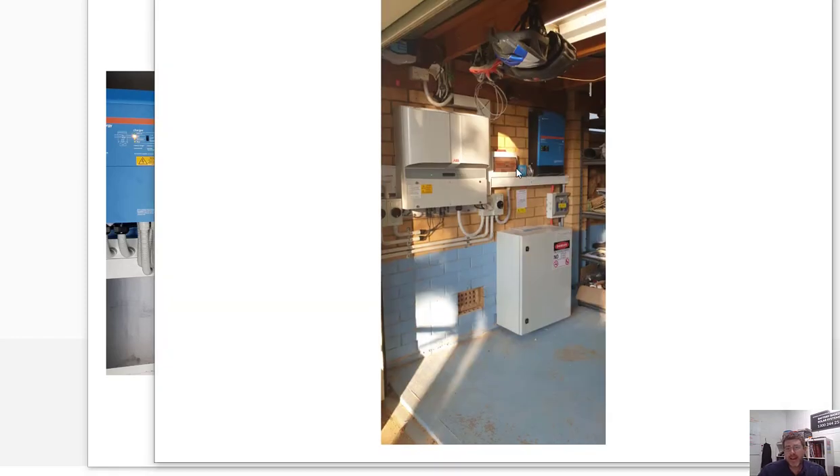Here's another really good example of a hybrid system we've installed. It's got a 10-kilowatt AC-coupled system — actually a three-phase system with 13 kilowatts of panels on the roof and a 10-kilowatt inverter. But it's actually a single-phase 5-kilowatt off-grid inverter. When the grid fails, this customer loses all three phases and then they've got backup on only single-phase — so lights, TVs, fridges, all that sort of stuff. And there are lithium batteries in here — we use the Power Plus batteries in this system.